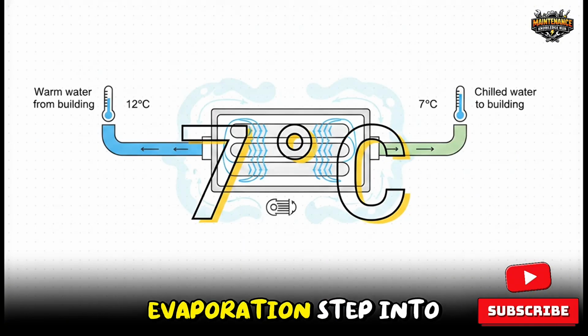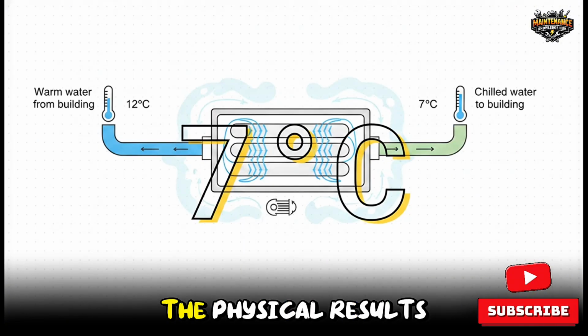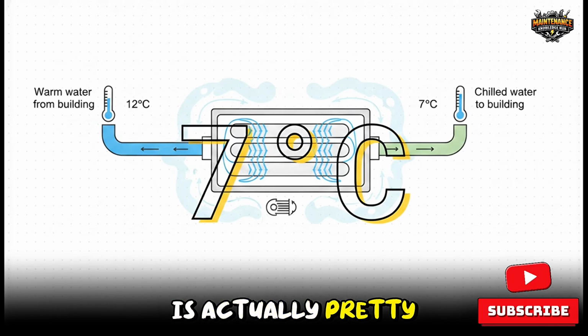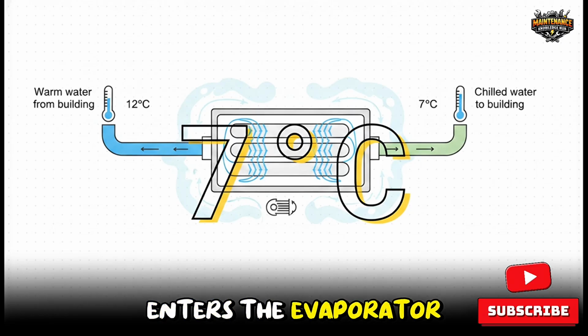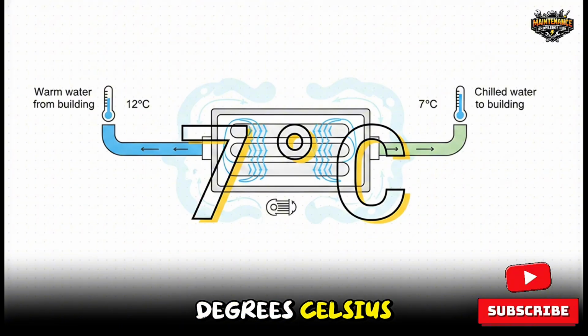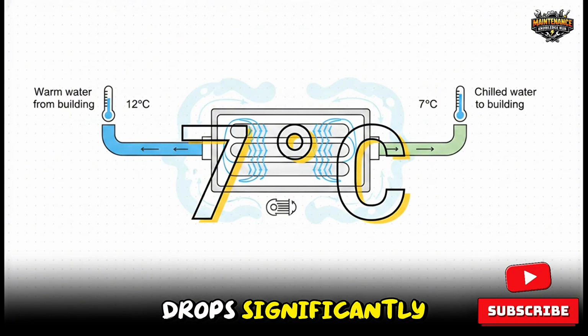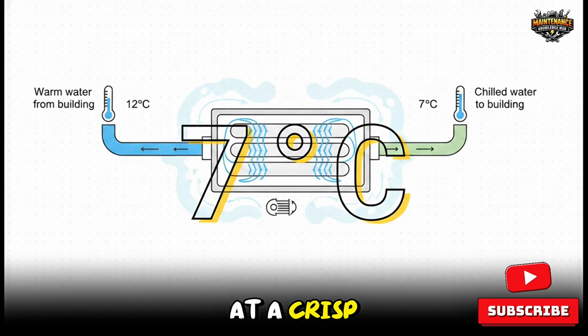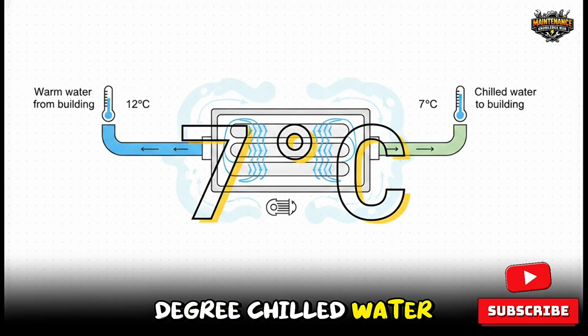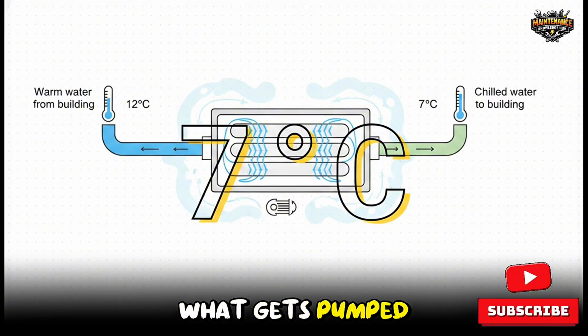To put that evaporation step into perspective, the physical result is actually pretty striking. The warm return water from your building enters the evaporator at about 12 degrees Celsius. As the refrigerant absorbs its heat, the water temperature drops significantly, leaving the evaporator at a crisp 7 degrees Celsius. And that 7-degree chilled water, that is exactly what gets pumped throughout the building to keep everyone comfortable.